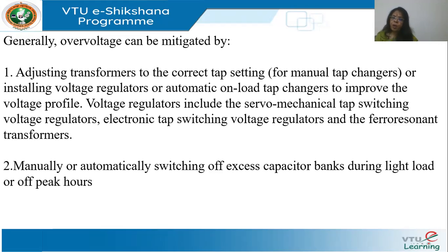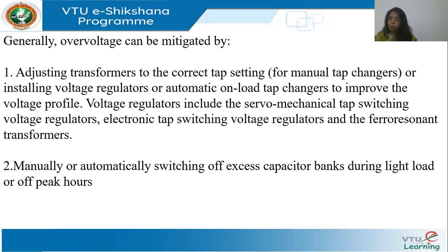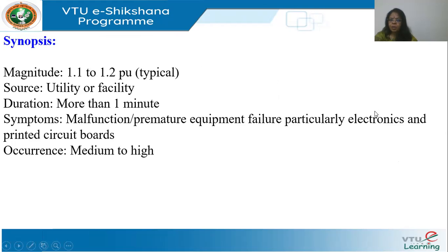The second solution is to switch off capacitor banks, as they are a major cause of over voltage under light load conditions. You may also need to introduce inductors or reactors to bring the voltage down from a high-voltage position. These are the two common mitigation solutions for over voltage.